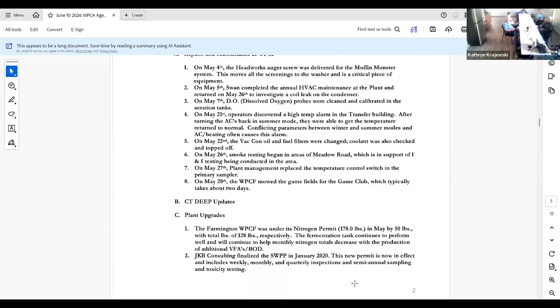We got the delivery for the Headworks auger screw. This basically moves the screenings to the washer. It's critical because the way the PLC works is when the rags and debris come into the plant, the bar screens rake them up, the auger pushes it in and then it's washed and goes in the trash. If any one of those doesn't work, the PLC says the rest of the system can't work, so we have to have spares for all of it. We do have workarounds with timers and other things, but if we can keep it going the way it should, it's much easier to work with.